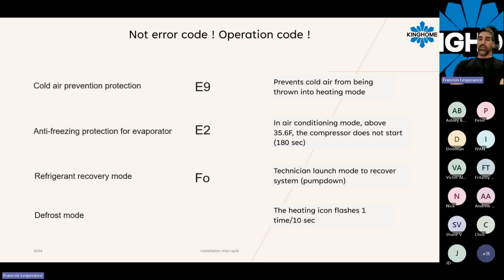The last thing is the defrost mode. So in the heating mode, the systems will run into defrost regarding the outdoor temperature, the outdoor coil temperature. When this mode is active, you will see, or maybe the customer will notify that the heating icon, so the little sun, is flashing, but in a very slow flash, like one time every 10 seconds during all the defrost period. So the defrost time can be somewhere between 1 minute to 10 minutes. Most of the time it will be around 3 minutes. But during that time, you can notice that the heating icon is flashing.